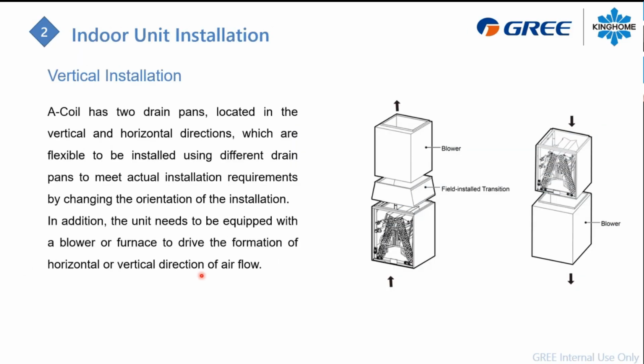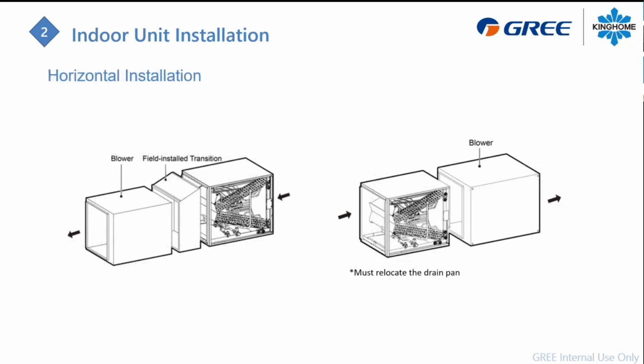And yeah, if it's installed vertically, your blower can be above the case coil, or it can be below. But in the case of an upflow or downflow installation, sometimes you will need to have a transition installed to fit the case coil, but just be aware that you need to fit the dimensions of the case coil. If it's a horizontal installation and it's a left orientation, you don't have to change anything on the case coil. But if it's a right horizontal installation, you must change the drain pan.